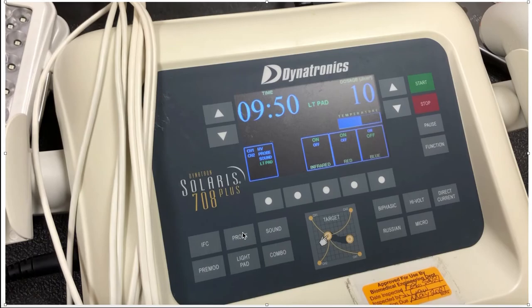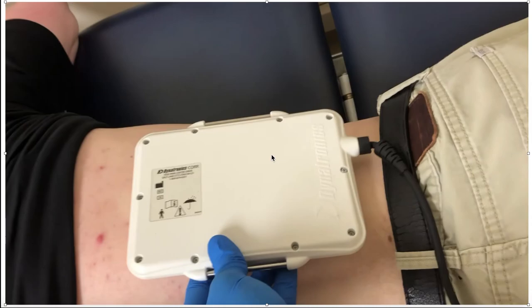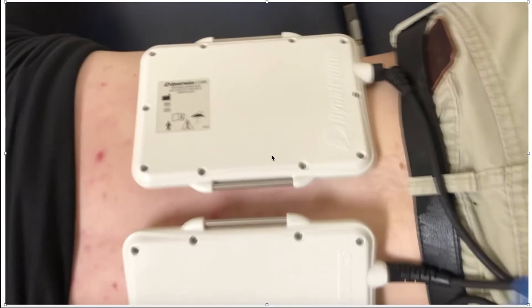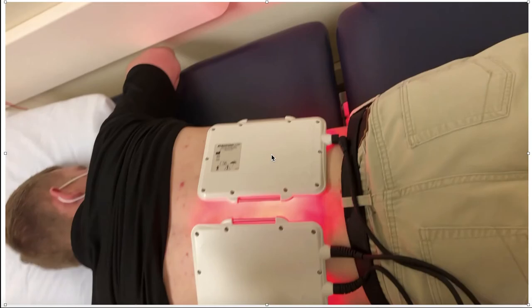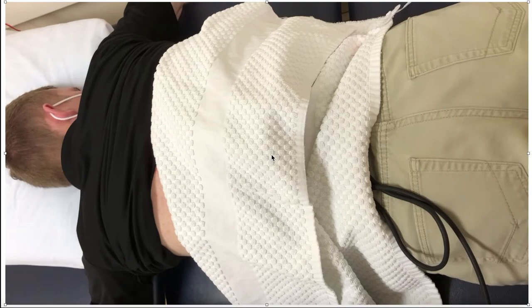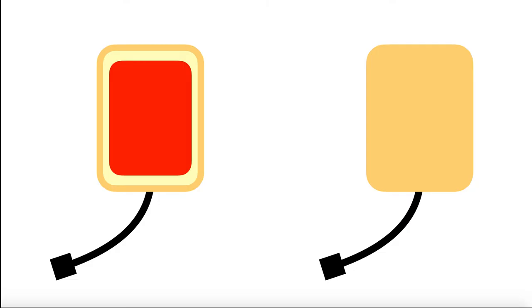Let's watch a quick video and see how that works. So here's our machine. I'm going to take these light pads you can see over here on the far left, and you just plug them in. You can see a little thing there that actually says light pad. So make sure that's plugged in all the way. And then over here, I'm going to select light pad. All those settings pop up. Everything's good. And then I take the light pads and I simply put them on the region of the skin that I want to accelerate healing with. So in this case, it's just lateral to the spine in the thoracolumbar region. And once they're on the skin and where I want them, I hit start. Once I hit start, you'll see the red light. Now, remember, that's not infrared. That's just red. But the red tells you that it's working. And I don't want that radiation to get in anybody's eyes. So we just take a towel and basically cover that. This guy's not at any risk of really looking into that light. But if somebody else is in the room, it's really just common courtesy to them. So we cover that to make sure that no light is able to get in anybody's eyes.